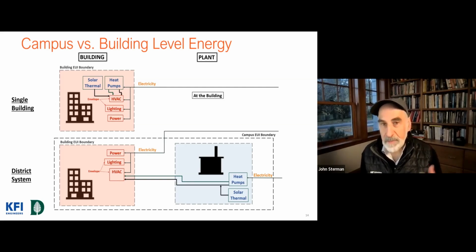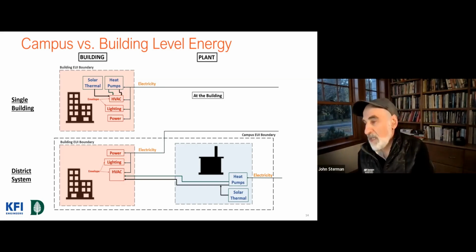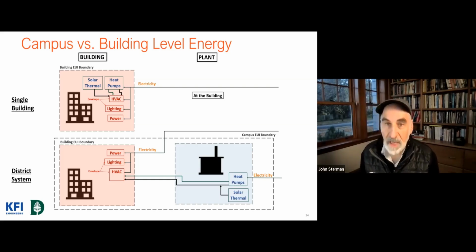It's a classroom office building with a big kitchen. Because we lowered the peak load so much—the design spec was 50%, the reality was 70%—that meant MIT, which provides steam and chilled water, didn't have to grow its capacity, even though we didn't convert to heat pumps at the campus level and didn't have solar thermal. It was the same old system.